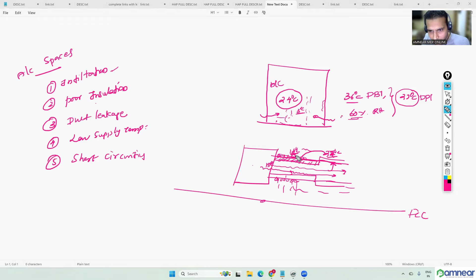That's a mistake. For example, the same issue: this 13 degrees Celsius air is traveling within the duct system. When this 13 degrees Celsius air is having contact with the metal duct, the metal duct temperature will be decreasing to like 13 or 14. So when the surrounding air is having contact with the duct surface, the dew point temperature of the surrounding air is much higher than the surface temperature. So when the air is having contact with this, dew will get created, condensation will happen. So your ceiling may fail.